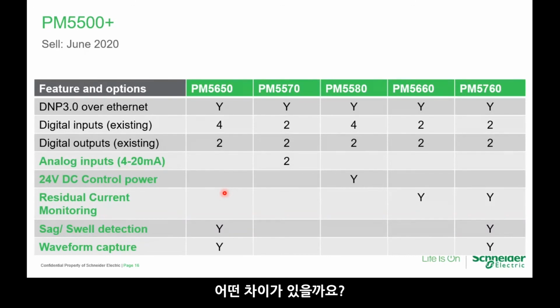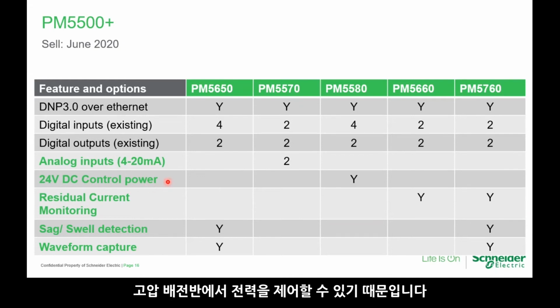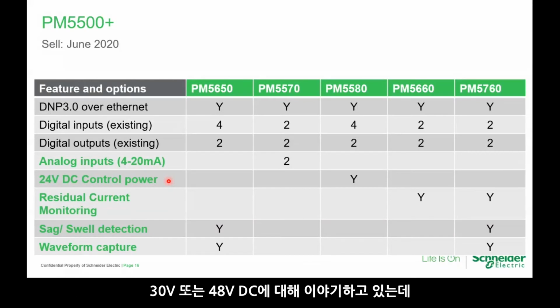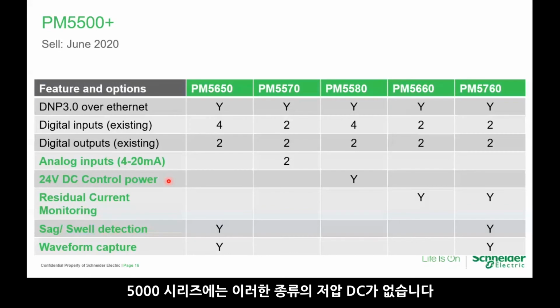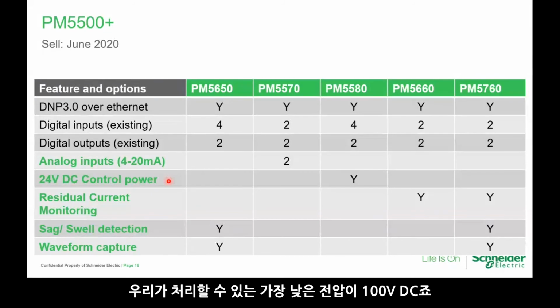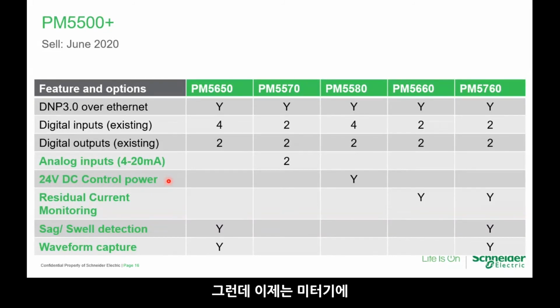So what are the differences? They are basically those highlighted in green. In the 5000 series, we are going to have a 24-volt DC control power. We need this because sometimes we may use it in medium voltage switchgear where the control power is 30 volts or 48 volt DC. We don't really have this kind of low voltage DC for the 5000 series - the lowest we can go is 100 volt DC. Now we have this 24 volt DC control power for the meters.